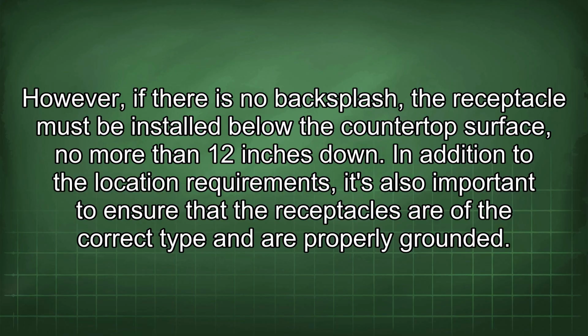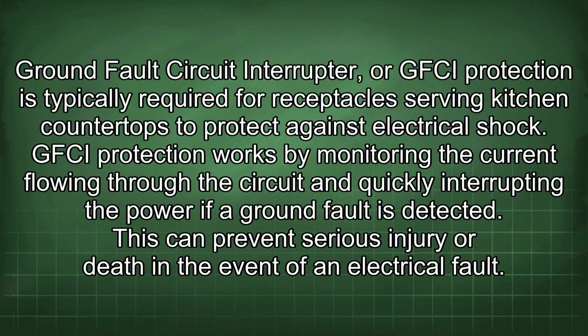and are properly grounded. Ground fault circuit interrupter or GFCI protection is typically required for receptacles serving kitchen countertops to protect against electrical shock. GFCI protection works by monitoring the current flowing through the circuit and quickly interrupting the power if a ground fault is detected. This can prevent serious injury or death in the event of an electrical fault.